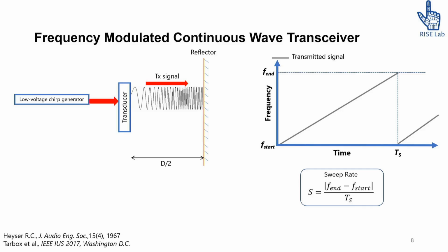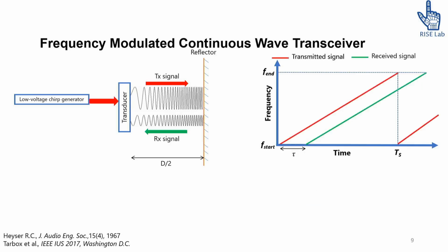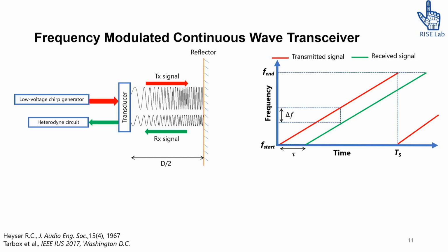So we transmit a low voltage chirp. This reflects back, and the reflected signal is also a chirp, but only delayed in time. However, this time difference can now be deciphered in terms of a frequency difference. This is very commonly used in the ultrasonic sensors that robotic applications typically use, but it has not been used in medical imaging. So this frequency difference translates to the time difference. We can use a simple mixing or heterodyning circuit to decipher this frequency difference, and it happens to be a lot easier to decipher than the time difference, because we don't have to measure time very accurately anymore.